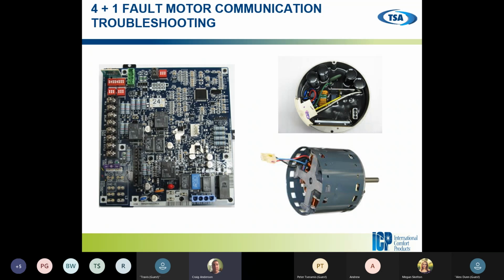So after it goes through our test signals, like I said, it's going to give you different faults, a 4+1 motor fault, communication trouble, things to look at. Your motor: did you put the chip back in when you changed the board? Are all the plugins in there securely? Things to look at.